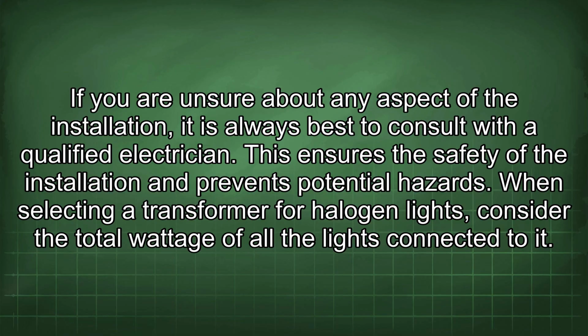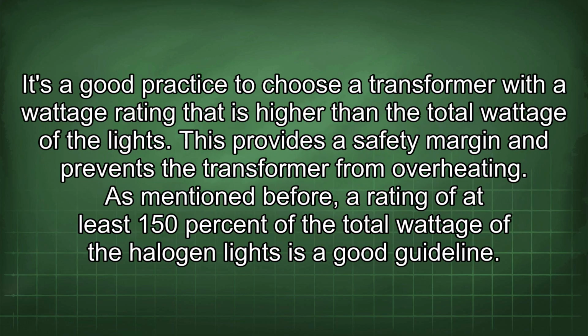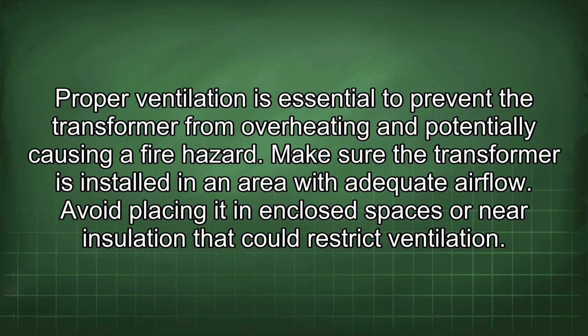When selecting a transformer for halogen lights, consider the total wattage of all the lights connected to it. It's a good practice to choose a transformer with a wattage rating that is higher than the total wattage of the lights. This provides a safety margin and prevents the transformer from overheating. As mentioned before, a rating of at least 150% of the total wattage of the halogen lights is a good guideline. Proper ventilation is essential to prevent the transformer from overheating and potentially causing a fire hazard.